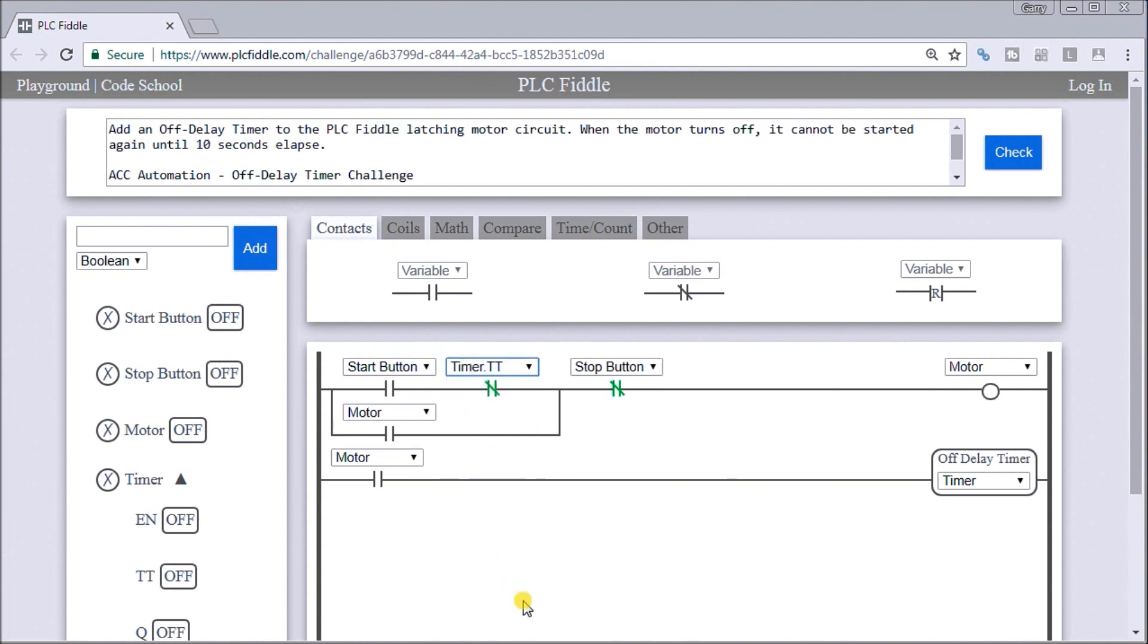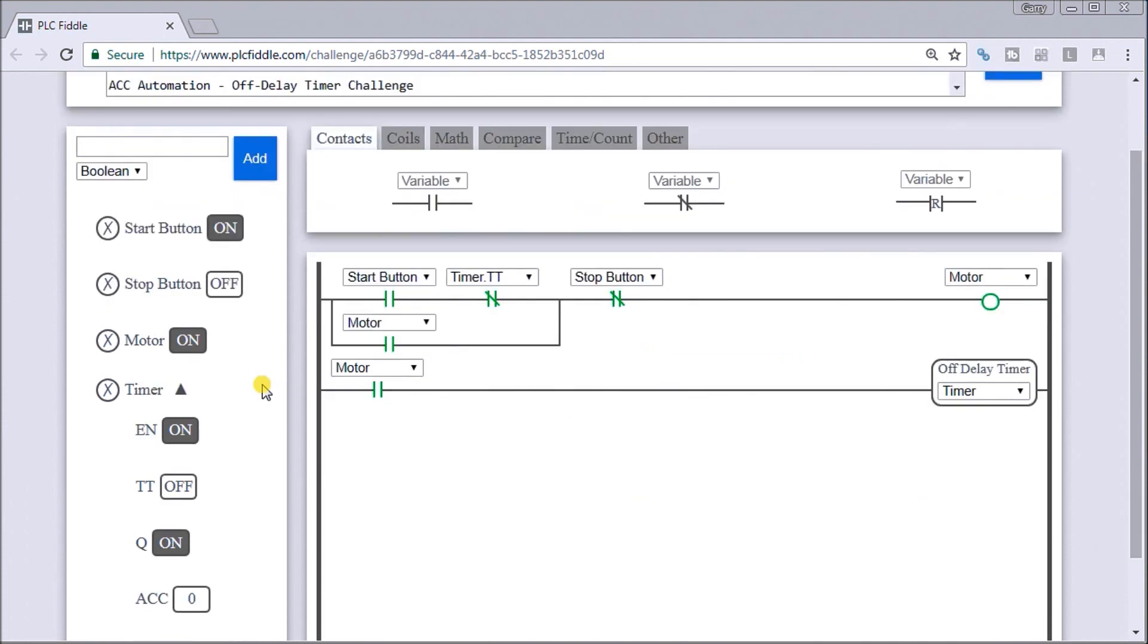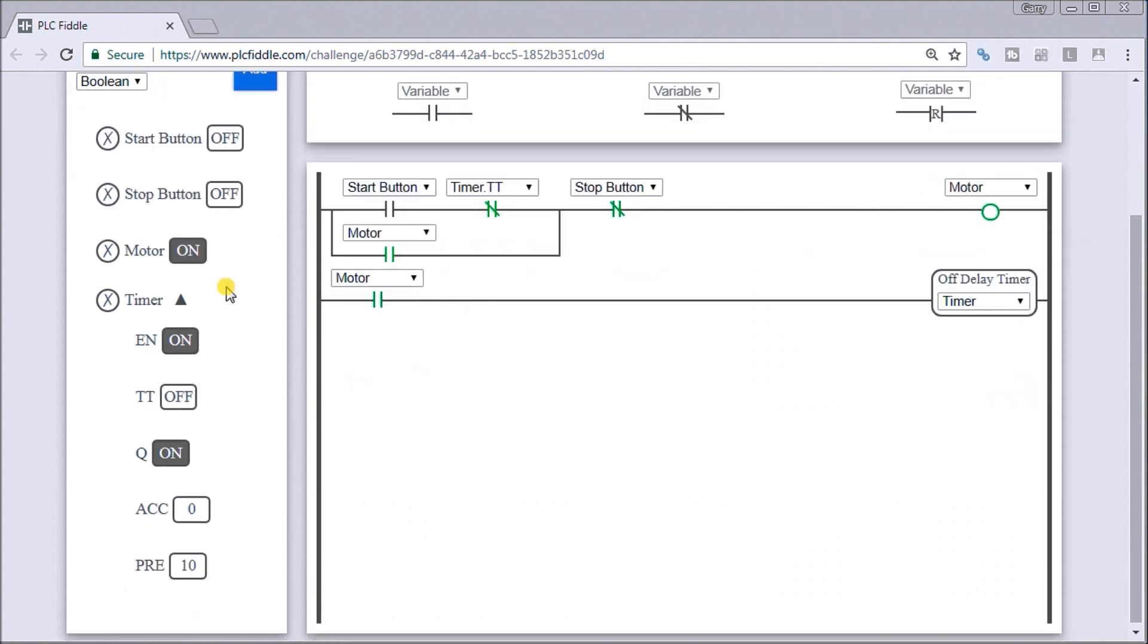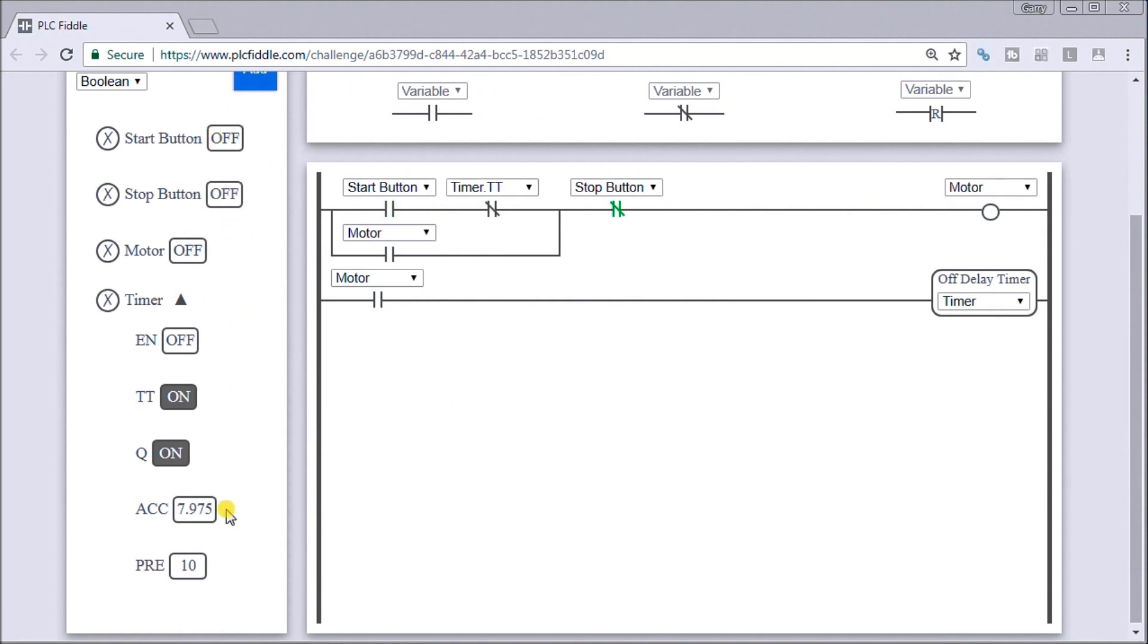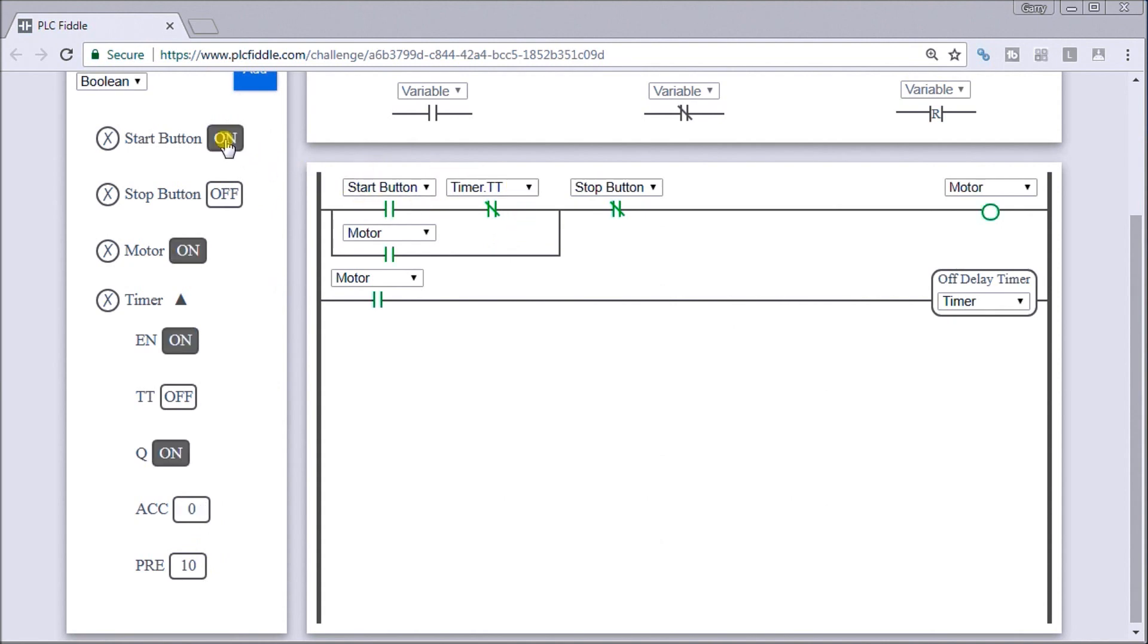I can now start my motor. The motor starts and what you'll see is when I turn the motor off, the timer starts timing. I will try starting it again - nothing happens until the accumulator reaches the 10. Now I'm allowed to hit my start again. The motor starts, turn it off, and the whole cycle happens again.